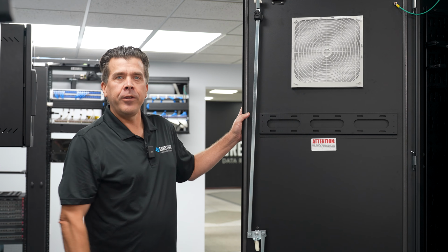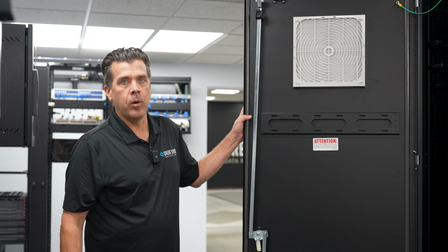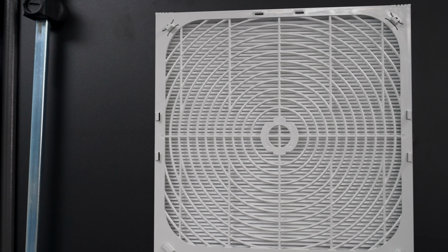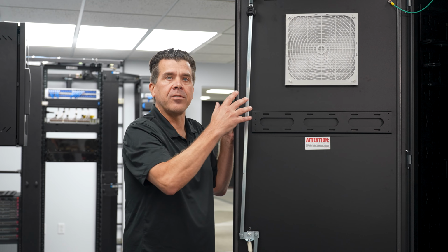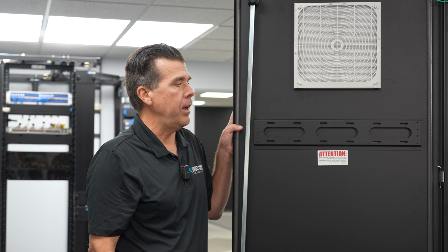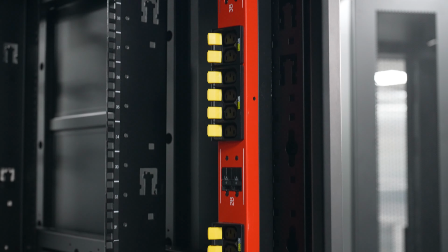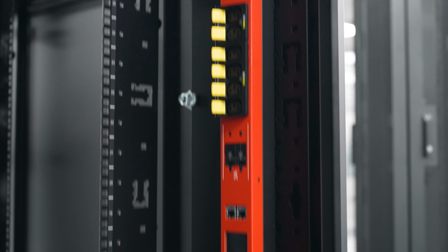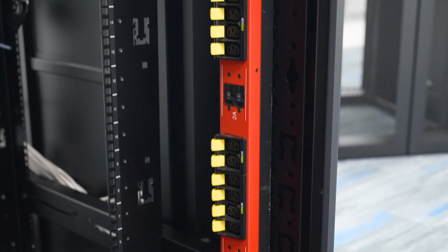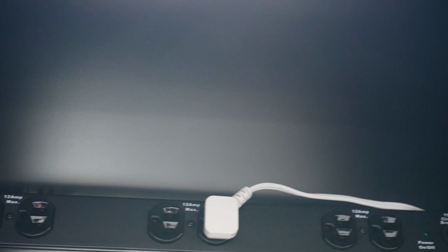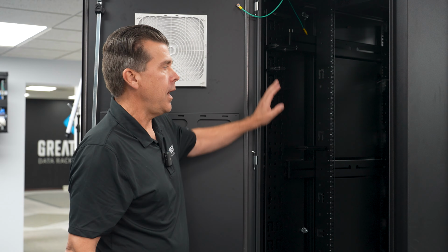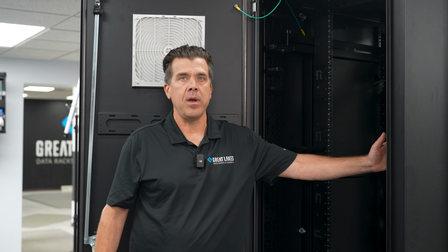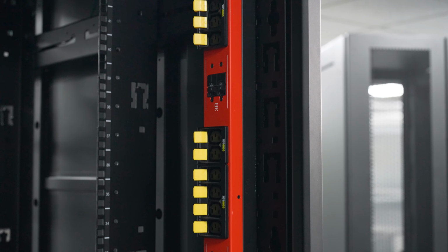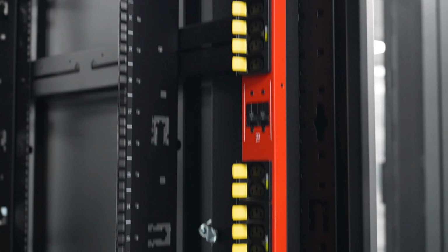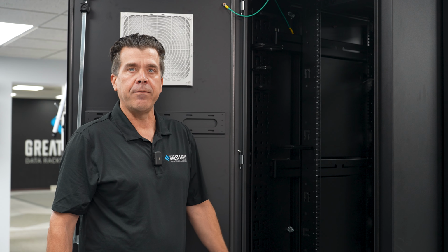These rails are an infinite adjustment that can be done very easily in the field before you rack and stack your equipment. Here on the NEMA-12 cabinet, we're looking at the rear door. You will notice that we do have a filter kit at the top of the door. This helps exhaust the hot air away from your equipment. Also, as far as the features, you may be concerned with cable management in the rear of the cabinet, as well as PDU mounting. The cabinet comes with standard lacing bars that can accept Velcro ties or toolless rings. And on this side of the cabinet, you see that we have a vertical PDU mounted. This is done with button-style mounting holes that will accept any vertical PDU.